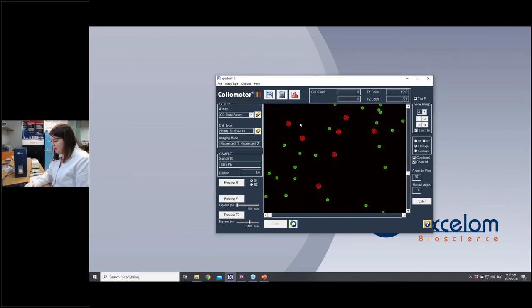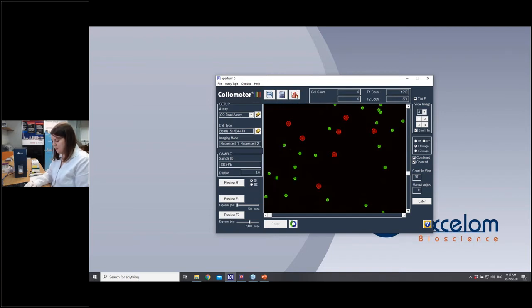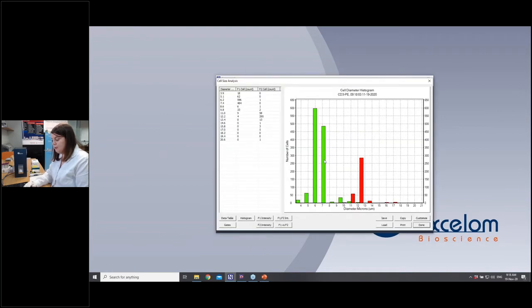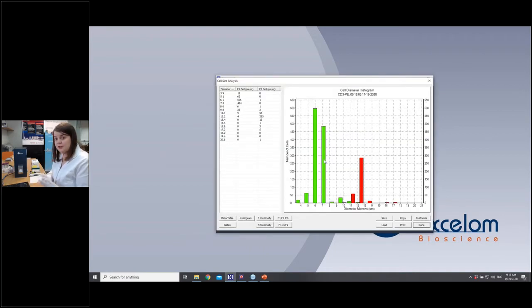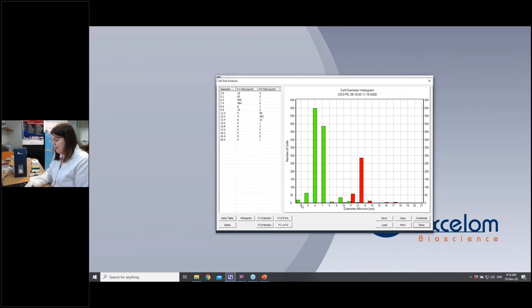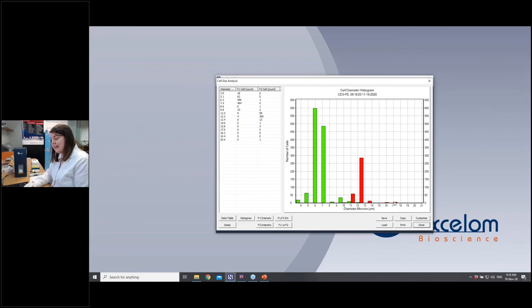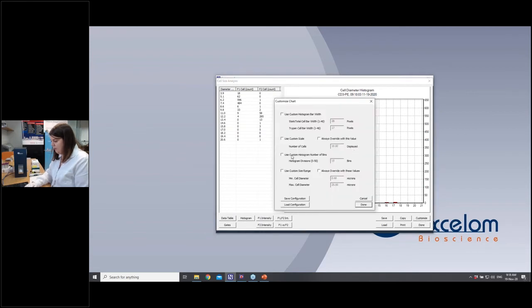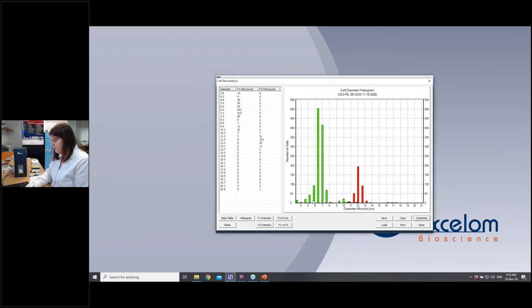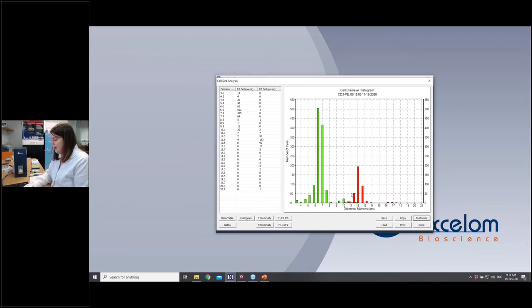There's a couple of other things that I wanted to show you on this. You've got your size histograms like I showed you in the presentation. So you can click on your histogram here and this will show you your size distribution of your beads or of your cells. So it's showing us here that the green beads are definitely smaller than the red beads. This again can be customized to suit exactly what you need it to suit. So if you wanted, for instance, if you wanted it to be a bit more in depth with the amount of bins that we've got, we can change that to make it look slightly different. You can also add gates as well. And I'll show you that with one of our cell samples.